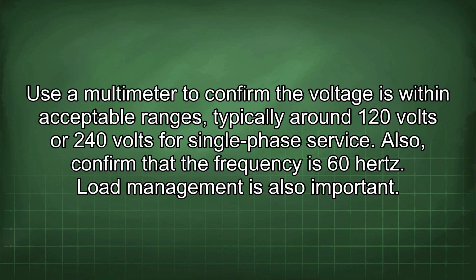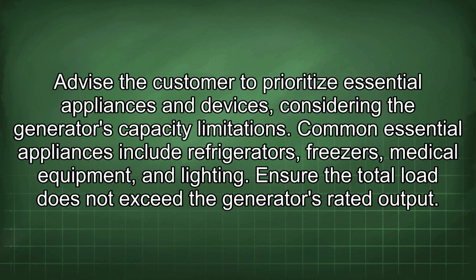Use a multimeter to confirm the voltage is within acceptable ranges, typically around 120 volts or 240 volts for single-phase service. Also, confirm that the frequency is 60 Hz. Load management is also important. Advise the customer to prioritize essential appliances and devices, considering the generator's capacity limitations.